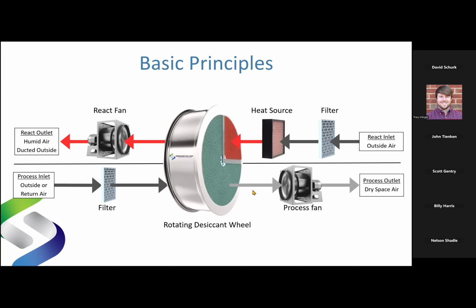Now, again, I mentioned it's fluted. Air flows through it in two directions. Our process airstream coming in can be 100% outdoor air. It can be 100% return air. It can be a combination of outdoor air and return air. It can be air as wet as you want to bring into that unit. The sky is the limit. You just can't stick a garden hose in the back end and get the wheel wet. The wheel needs to stay physically dry, and it always will, done right.